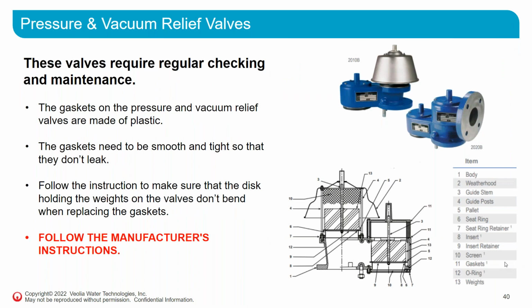So these valves require regular inspection and maintenance. They typically consist of a thin plastic gasket with some weights on it to hold it down, so they can degrade over time, or if they're not installed properly, you could have leaks. So it's important to follow the manufacturer's instructions for both installation and inspection. It's a good idea to have the manufacturer come out the first time you do it and show you how to do it, because they can be different, and then you will know going forward what the proper way is to inspect and repair them.